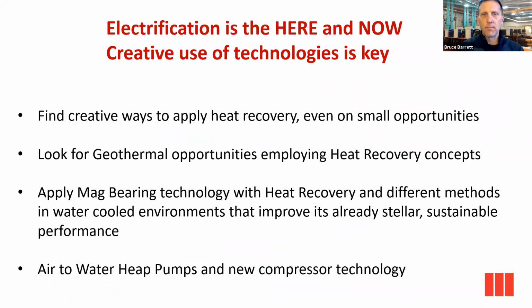All right, so just a quick summary. Not only does ASHRAE require it for hospitals, but it makes really good sense to use heat recovery, to apply it in different applications. It's a great way to save energy over the best boiler that you have out there. Continue to look at opportunities to move your temperatures down, move your COP up. Look for geothermal opportunities, employing the heat recovery concepts.